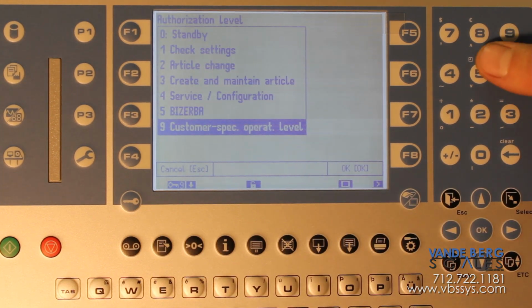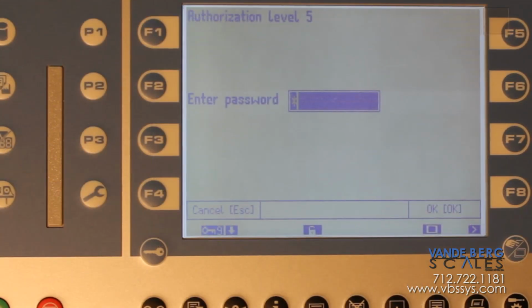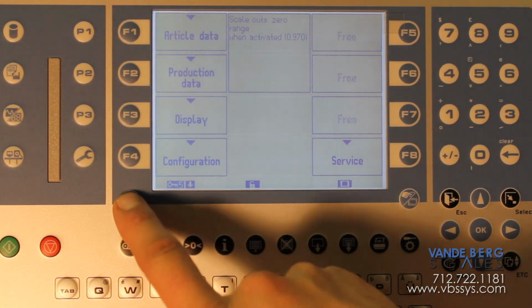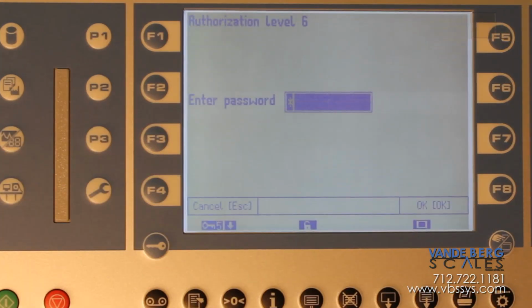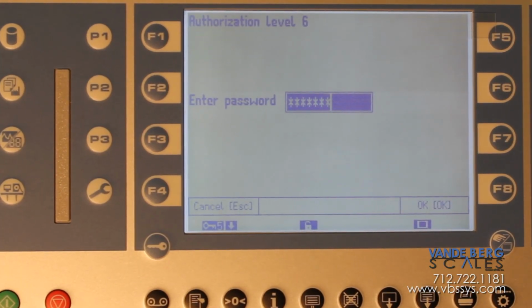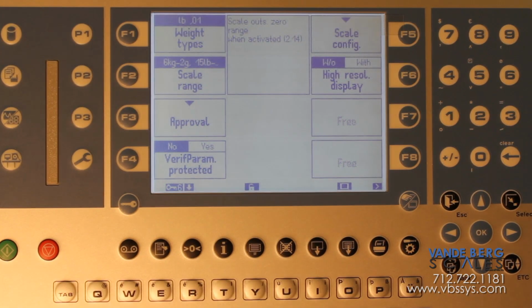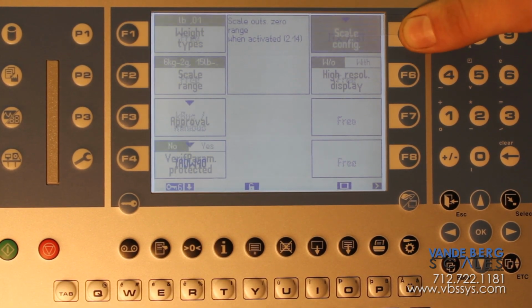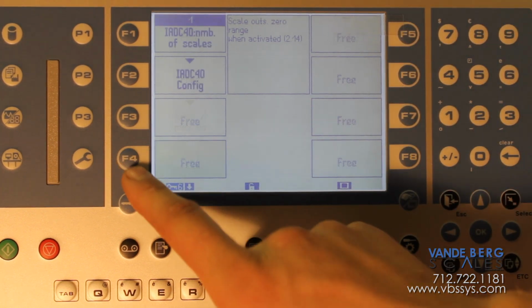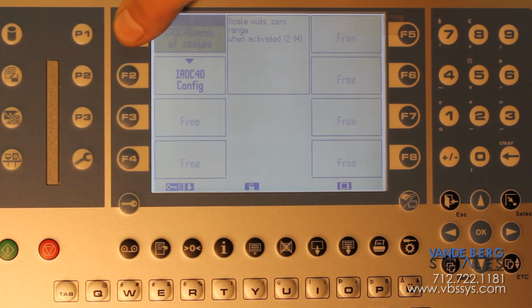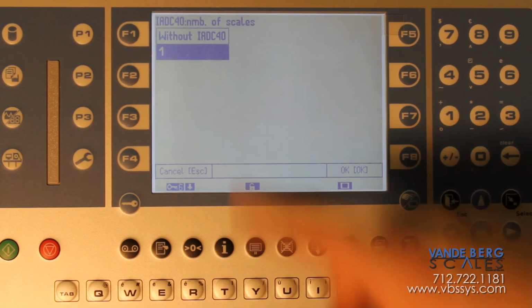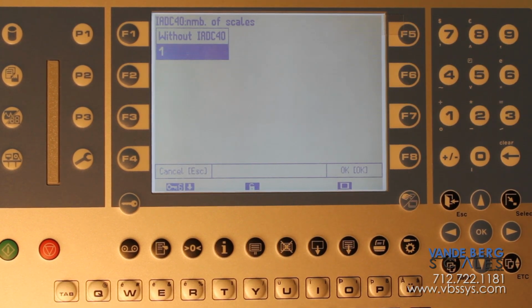For that, we'll first go into mode 5 again, enter the password. Once we're in mode 5, now we can go into mode 6. Once we're in mode 6, we'll go to scale configuration and the IADW40 and the IADC40 number of scales. Sometimes this will be set up and say without IADC40. This one was default on one scale already. If it is set to default on without IADC40, you'll need to change it to 1 and then it'll ask you to reboot.